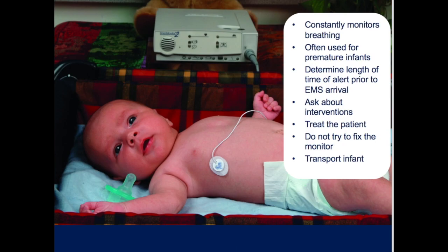Something else you will probably encounter is something called an apnea monitor. Let's start with what apnea is. Apnea is, by definition, the temporary cessation of breathing. So little infants is where you're going to see these apnea monitors, and quite often it's premature infants who get sent home with the apnea monitor. These monitors monitor the breathing of the patient, and they can also monitor heart rate. If there are abnormalities in the breathing or the heart rate, these apnea monitors will get triggered and let out a noise, say a beeping noise. The noise can be different, but the beep can progressively get louder or more frequent the longer the alert sounds, in case the parent's not in the room to immediately hear the alarm.